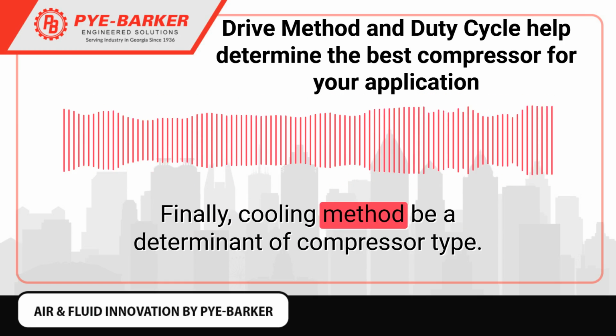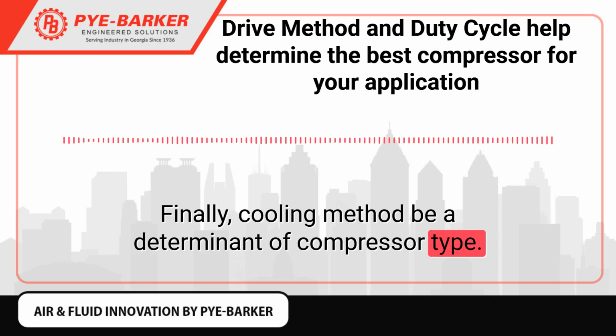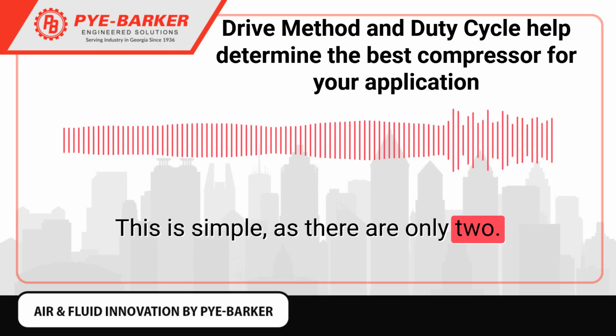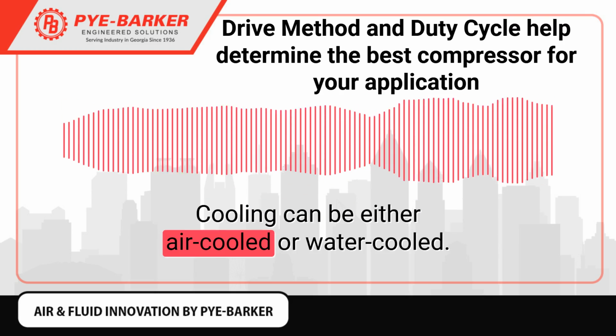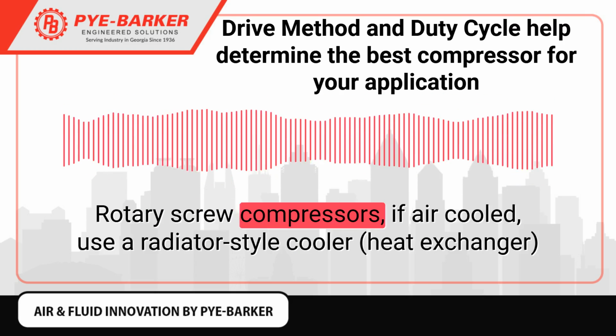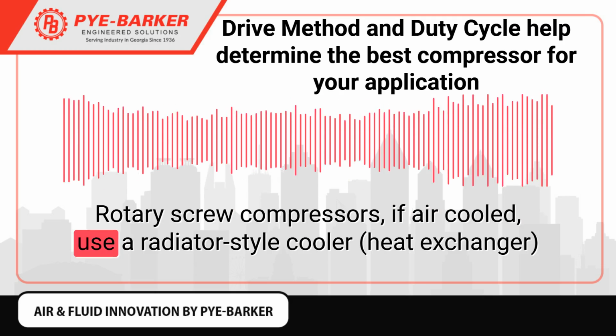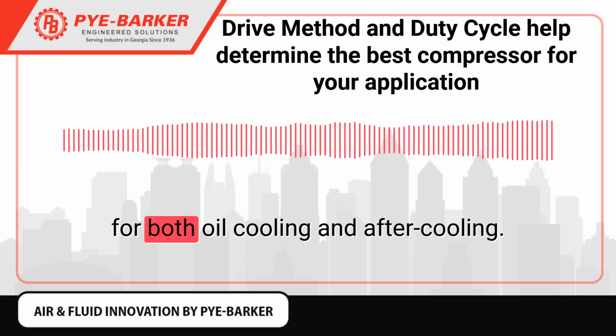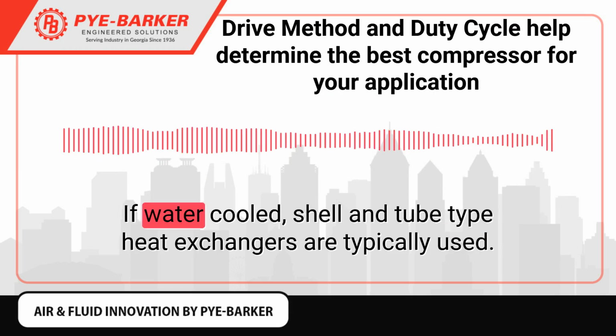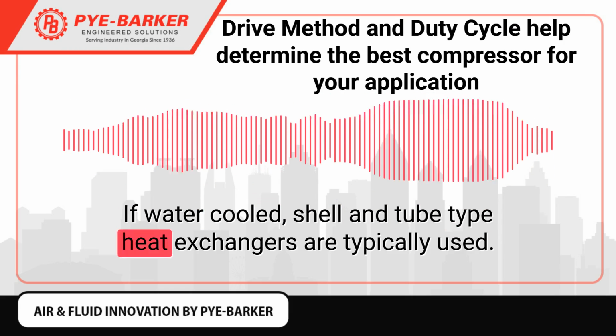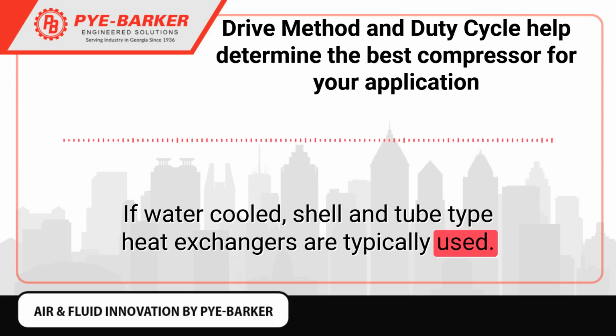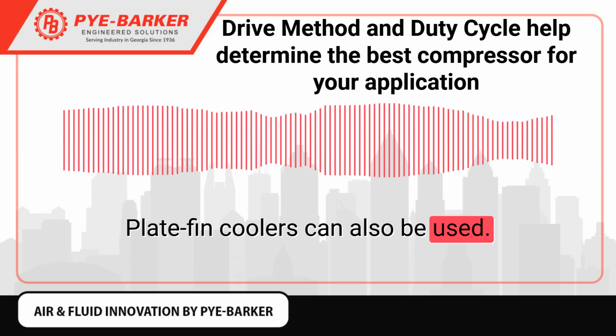Finally, cooling method can be a determinant of compressor type. This is simple as there are only two. Cooling can be either air-cooled or water-cooled. Rotary screw compressors, if air-cooled, use a radiator-style cooler for both oil cooling and aftercooling. If water-cooled, shell and tube-type heat exchangers are typically used. Plate fin coolers can also be used.